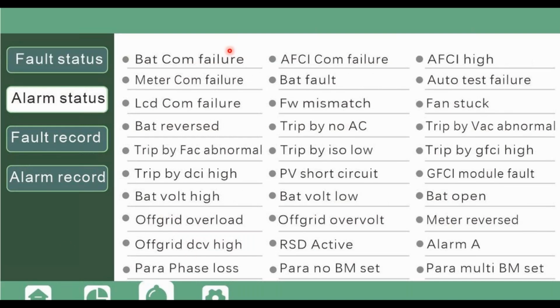Okay. Same with alarm. One of the things that we've gotten a lot is that, let's say you have battery open, right? It could be something simple, as the inverter is recognizing the battery, but you just haven't turned on the battery breakers. So that's what battery open would mean. Or, let's see, trip by no AC. When you're commissioning the inverter using our battery, you might see this first warning say trip by no AC. It means you have no grid going in. So just a couple things that it could be, no biggie. But if you are stuck, again, don't hesitate to give us a call.